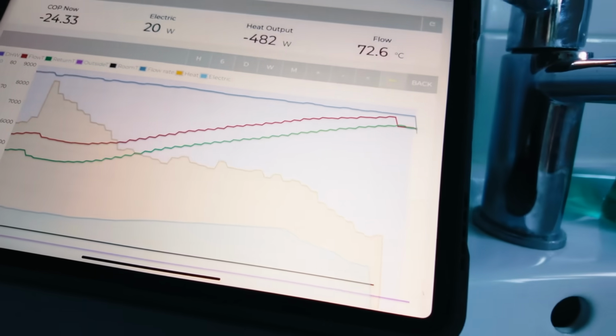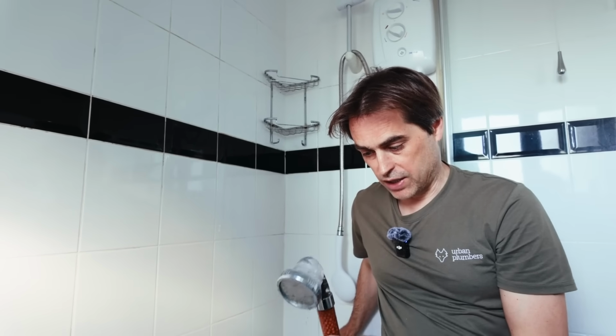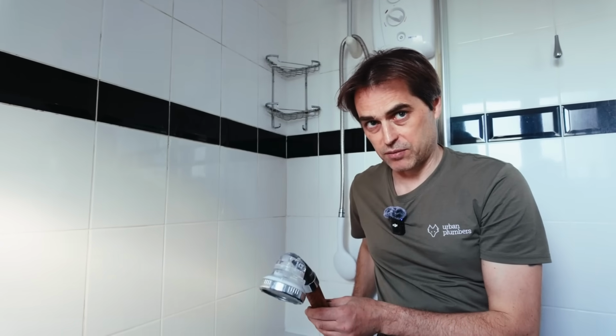You can see the heat pump has stopped now. Yeah, so it's up to temperature. We've turned on the shower. We want this to run, but importantly, we need to see the heat pump kick in before we get a drop in temperature. If it doesn't kick in before we get a drop in temperature in the shower, then it's not really a combi, it's just a really small store and probably won't be of any use to anyone. So, there we go. We're gonna time it and run it with this water-saving shower head. I think we're gonna get about 7 liters a minute from this.